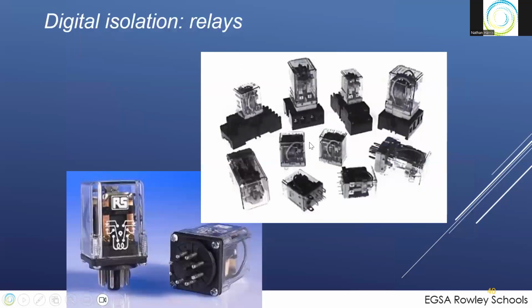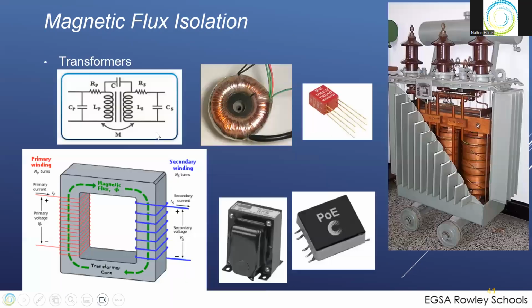To get this galvanic isolation, you can do it digitally with relays. That's most obvious. You energize a coil, the contact closes, those circuits are totally isolated from each other. It's a way to share information from this circuit to that circuit. Maybe it's a 24-volt coil and a 120 volt. So different systems, different voltage levels, but still it's a way to provide this galvanic isolation between the systems.